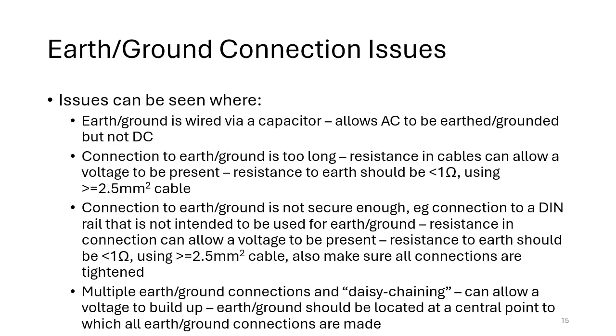So here's some more detail of these earths or grounds and the sorts of issues you might face. Something you need to be aware of is that sometimes the earth or ground is wired via a capacitor. The idea is a capacitor allows an AC signal to pass, so that eliminates AC noise, but if you've got that capacitance there, it doesn't eliminate DC noise. So if you've got some DC circuits, if it's below 40 volts, again, that might not be a problem, although there might be enough voltage there to actually overcome the resistance of some circuits and cause damage to the circuits.